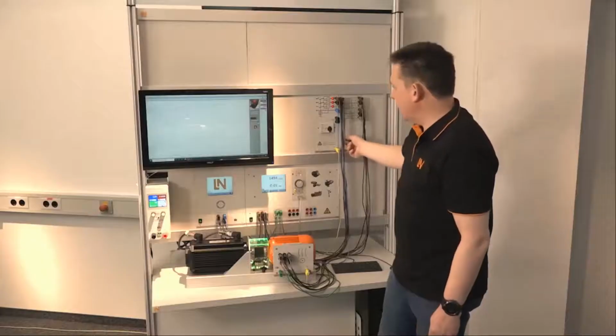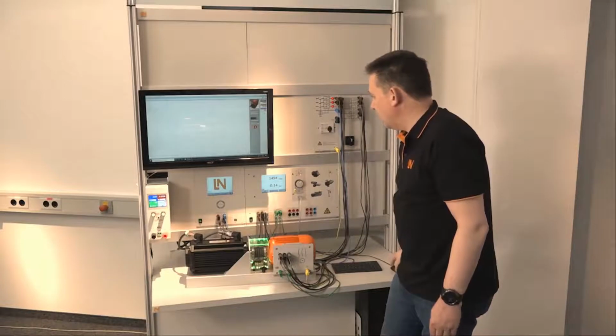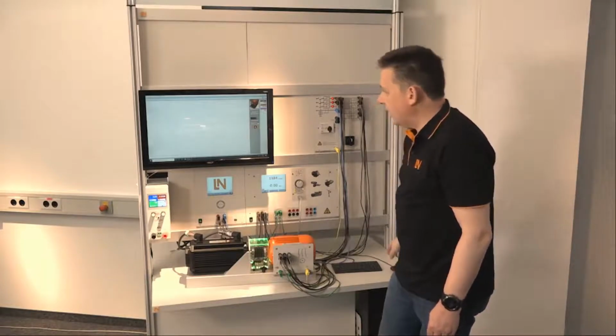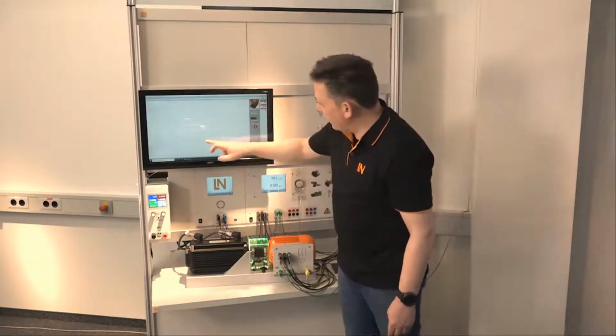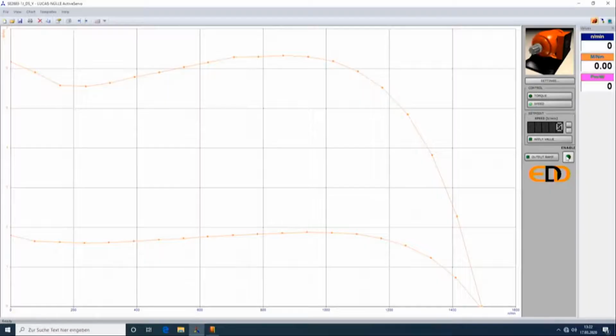So I will switch off the motor and the software also, and what we see here is we have a big difference between the two torques. And so we see, okay, if the motor runs in Y connection, star connection, the torque would not be as high as in the delta connection.